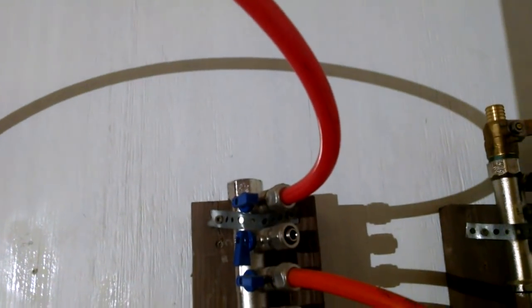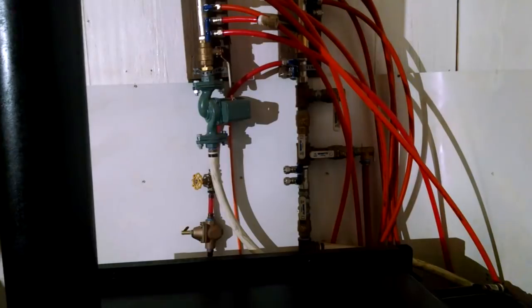Okay, another exit here. This exit actually goes to an expansion tank. The function of the expansion tank is to hold the extra water when the water expands with heat. The idea here is that if we have 5 gallons of water inside the heat exchanger, maybe another 5 gallons under the floor in the tubing, and you heat the water by about 100 degrees, from room temperature to about 160, you will get thermal expansion of about 1% by volume. That means about 500 milliliters, about a pint of extra water. The expansion tank allows the water to be captured without leaking out of the system.